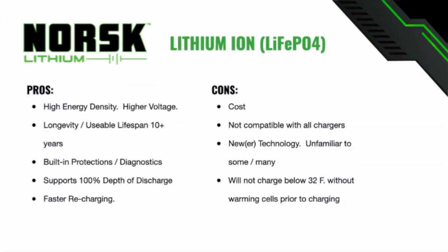On the lithium side, we've got built-in protections. You're not going to be able to overcharge it, and you're not going to be able to under-discharge it, because there's a brain sitting on top of that battery called the BMS, Battery Management System. It controls everything going on inside that battery: how much current it can deliver, how long it can deliver that high amount of current, whether it can take a charge below a certain temperature, and whether it will operate at extremely warm temperatures. It's kind of like having a guardian angel, making sure the user isn't abusing that battery.